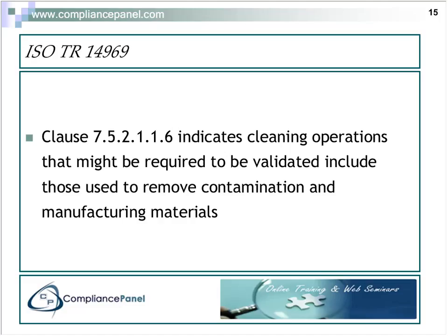So it says clause 7.5.2.1.1.6. Well, which one is that? Well, the 7.5.2.1.1 is that clause in 13485. And then the .6 is a discussion on that particular clause in 13485.